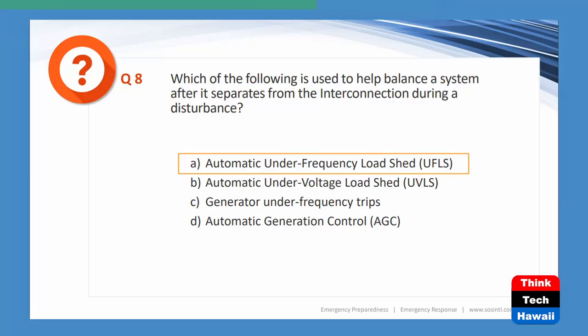The reason B is not exactly a correct answer is, now, mind you, that may take effect, but under voltage load shedding usually happens in certain pockets, right? Certain areas in your system, not widespread. Under frequency load shed happens at almost every single distribution station that you have in your system. So that's why automatic under frequency load shedding is likely the answer here, which is A.